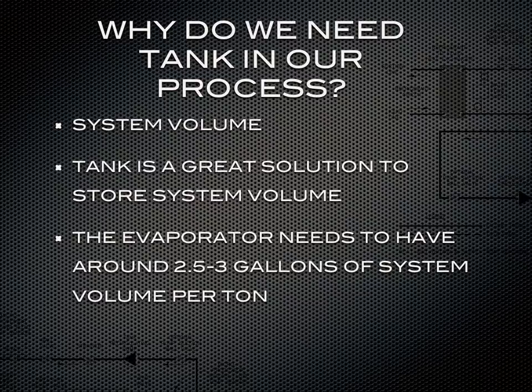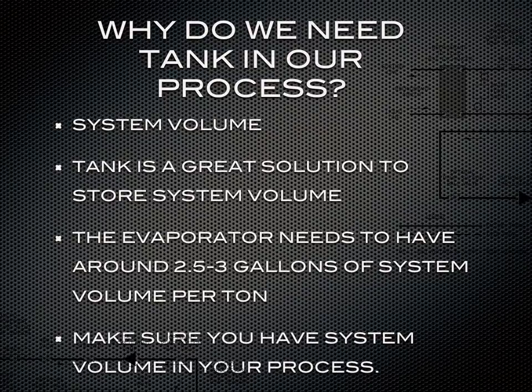For example, if you have a 5-ton chiller, there needs to be around 15 gallons of system volume. If you have a 30-ton chiller, there needs to be around 90 gallons of system volume. A lot of people go off 2.5 gallons of system volume per ton. We recommend 3. If you don't have enough volume in your system, you're basically going to shut down your refrigeration system by short cycling the compressor. Once your refrigeration system goes down, you're not going to be able to cool your piece of equipment. Always make sure you have enough volume in your system.